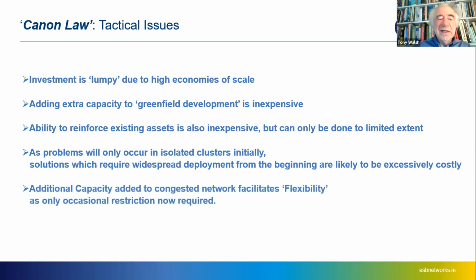Additional capacity means that you increase the scope to use flexibility. If you have a very congested network and try to use flexibility, you'd be turning everybody on and off every 5 minutes because there wouldn't be enough capacity to go around. When you add extra capacity, it means you only have congestion maybe once a week, so your restrictions on what you need to do are much less.